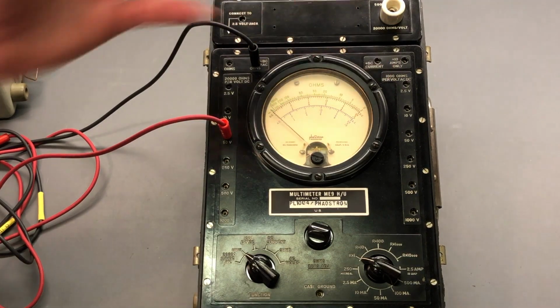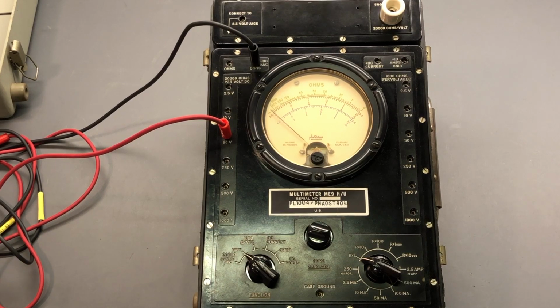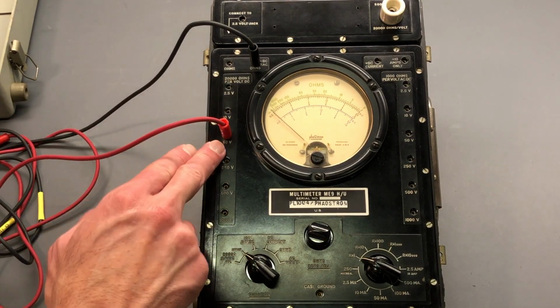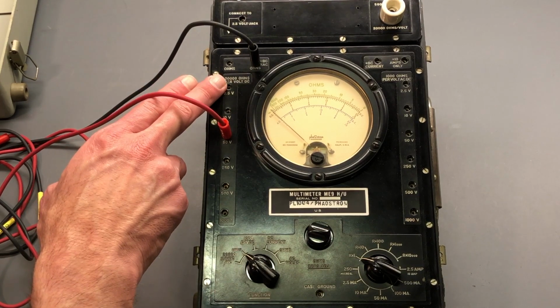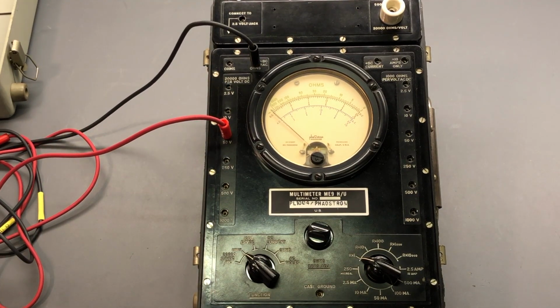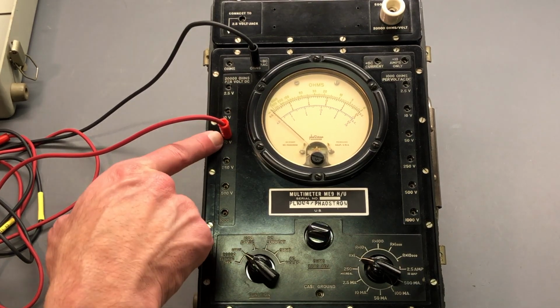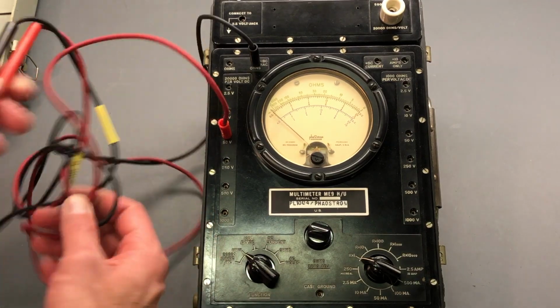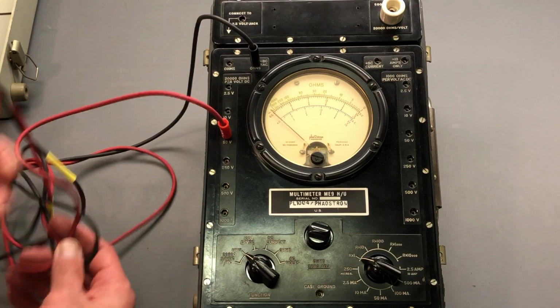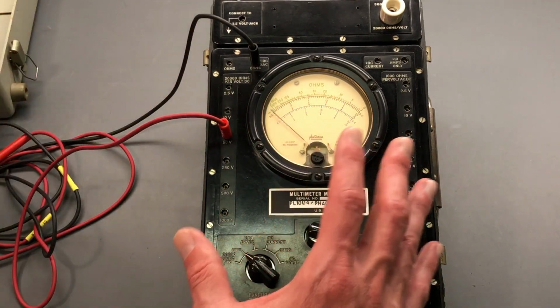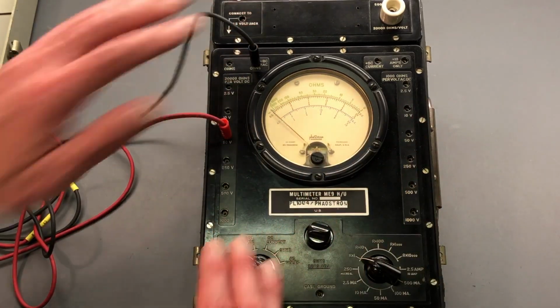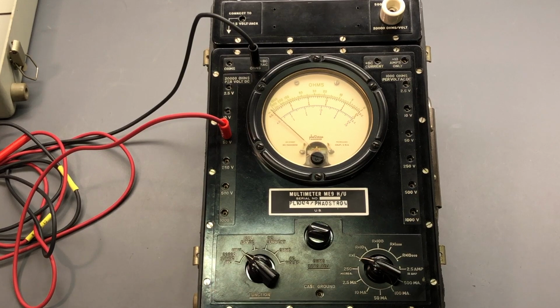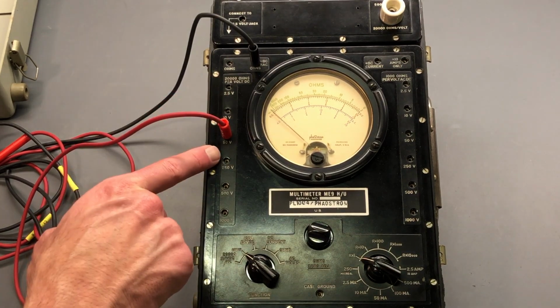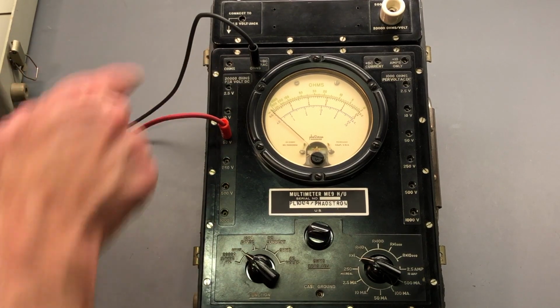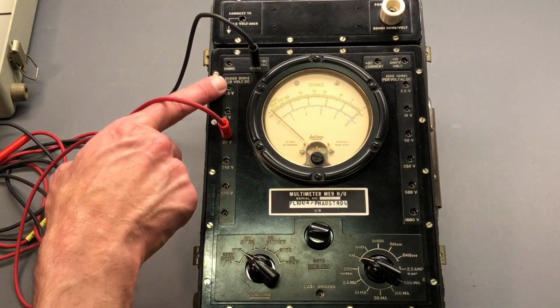So we have 20,000 ohms per volt and 1,000 ohms per volt. So again, 20,000 and 1,000. And what does that mean? Well, it's basically telling us the input resistance that the meter has. So with 20,000 ohms per volt and 50 volts, you just multiply 50 times 20,000. So 50 times 20,000 is 1 megohm, or 1 million ohms. So that's telling us that on this connection right here, between these test leads, we have 1 million ohms of resistance that this meter would apply, or that the circuit that you're testing would actually see. It would see 1 million ohms. Pretty high, not as high as a lot of modern meters, but fairly high. That resistance goes up for 250, 500, 1,000. Take those numbers, multiply them by 20,000, and you'll get the resistance of those ranges. Something lower is obviously under 1 megohm.